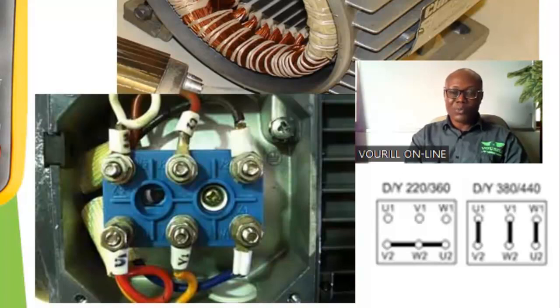And then you also want to check for open circuit. Now if the winding is shorted to ground, you can actually carry out your continuity test while you have all the shunting bars on. You just take your meter to the continuity selection of your digital multimeter, and place one probe on the terminal of the cable of the motor, and the other to the frame. If any of the winding is shorted to ground, you will hear the beep, since all of them are connected, as you can see on the shorting bar. When you disconnect like this, you want to see which particular winding, whether it is the U, V, or W winding, that is shorted to ground.